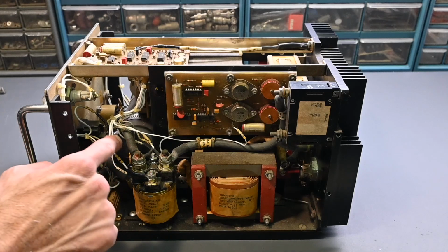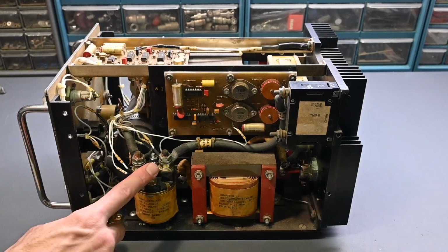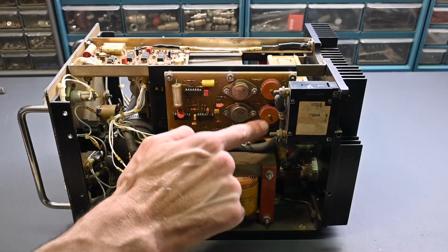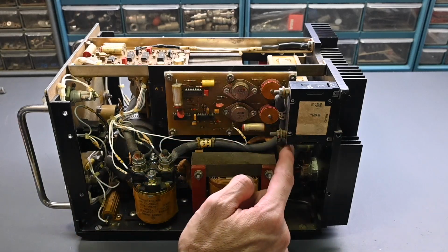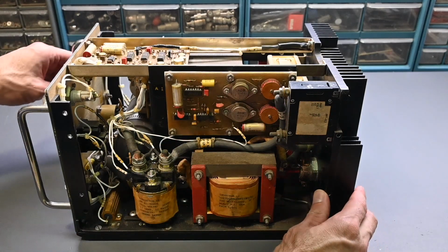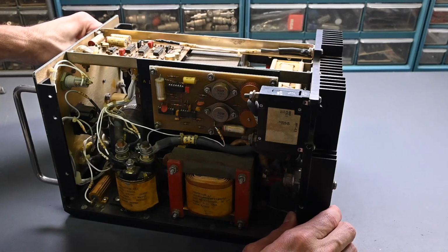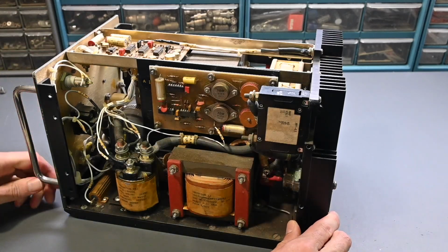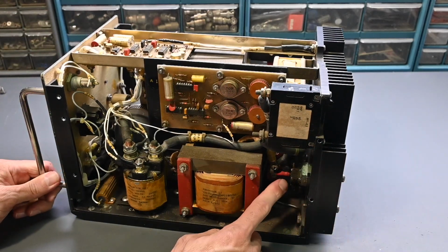It looks like this heavy gauge wire comes in, goes through the contactor right here, comes over to the breaker, out of the circuit breaker, and goes down to the power devices on the back. Kind of gets lost down in there, but what do we see in this corner right here?